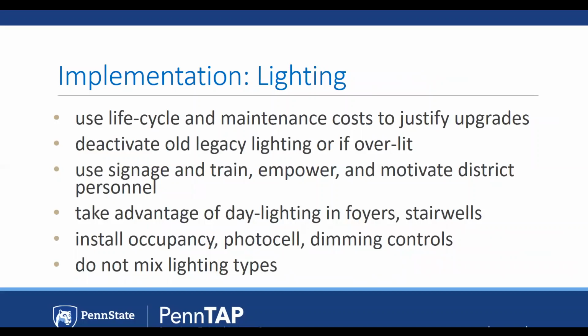For lighting, take advantage of the life cycle of the bulb, and use maintenance costs to justify upgrades. Deactivate old legacy lighting, or lighting where you're overlit. Use signs, train, empower, and motivate your district and municipality personnel. Take advantage of daylighting in foyers and stairwells. Install occupancy sensors or photocell dimming controls.